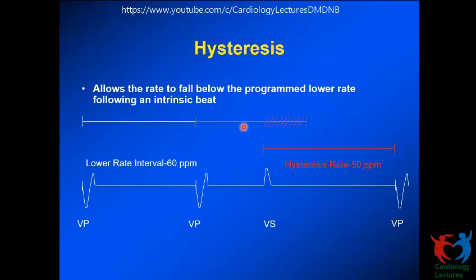As the lower rate is running, it saw a V sense, and on V sense, when hysteresis is on, it does not start a lower rate interval, but it starts a hysteresis rate interval, which in this case is longer, which is 1200 milliseconds. So here it waits for 1200 milliseconds. If no intrinsic event comes for 1200 milliseconds, it delivers a V pace and it will start a lower rate interval here. But imagine now at 1100 milliseconds, there is a V sense here. Now it will restart a hysteresis interval.